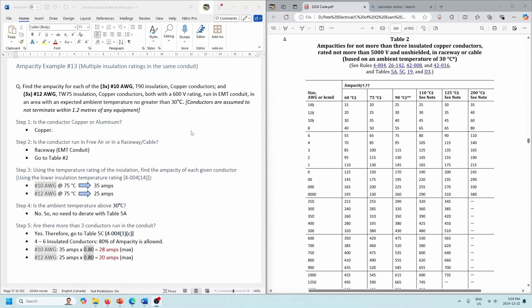Example thirteen: multiple insulation ratings in the same conduit. We've got three number 10s — they're T90 insulation, copper conductors. And then we also have three number 12 conductors, but they're going to be TW75 insulation — also copper conductors. Both the T90s and TW75s have 600-volt ratings. They run in EMT conduit, so we're going to be looking at Table 2. And we're not going to worry about ambient temperature here — just T90 insulation and TW75 insulation.